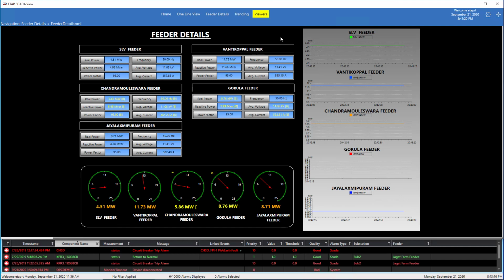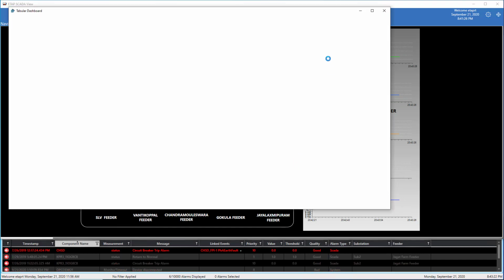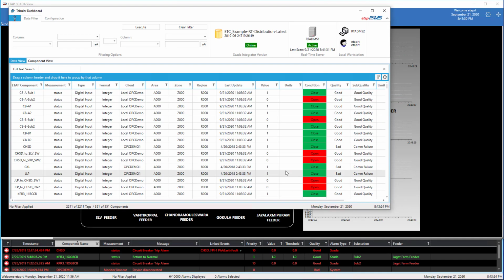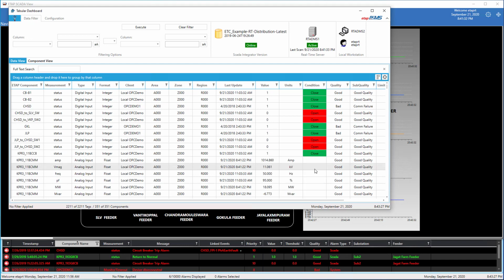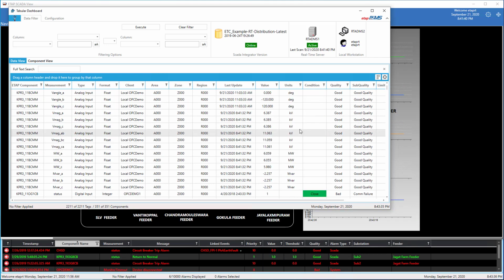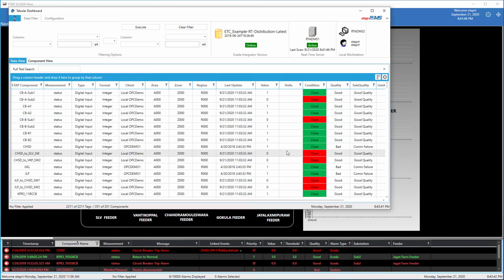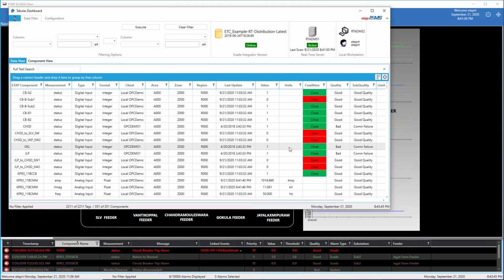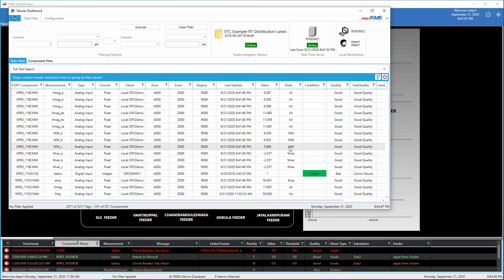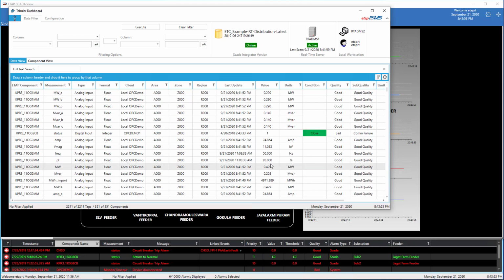Then we go into the Tabular Dashboard. Tabular Dashboard is another view that allows, at the substation level, to view all the signals in the system and understand very quickly what the status is, what's open, what's closed, what's in good quality. For example, if there are communication failures, you can see them here right away. You can see all the measurements. This is automatically created. It's basically looking at the communication channels of the ETAP system, the ETAP real-time server. So all that information is tabulated automatically. You don't have to manually create this table.